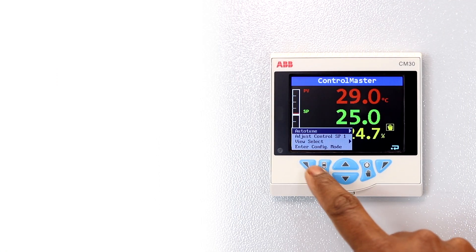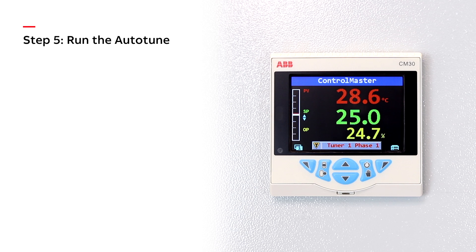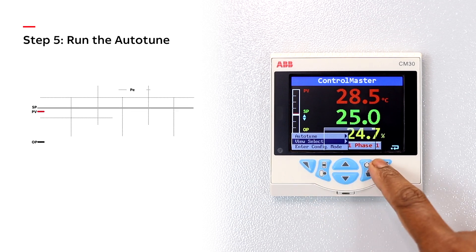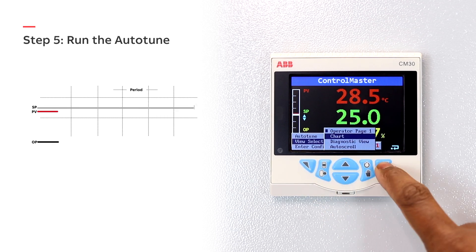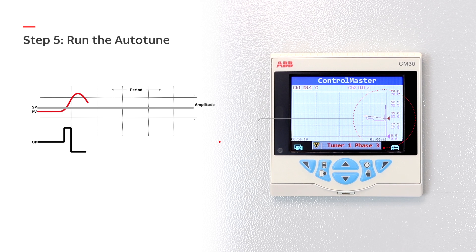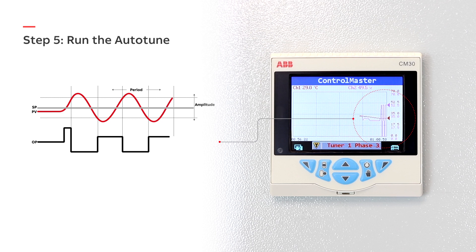Step 5. Run the Auto-Tune. Auto-Tune steps up and down the controller's output to create a controlled oscillation of the process. Based on this oscillation, optimum PID values are automatically calculated.